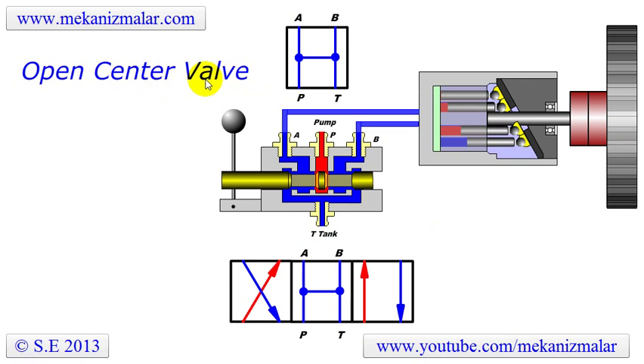This valve has four ports. Port P is connected to a pump which supplies pressurized oil to the valve. Port T is connected to the tank which contains low pressure oil to be pumped to the circuit. Port A and port B are connected to the device to be controlled, in this case a fixed displacement piston motor.